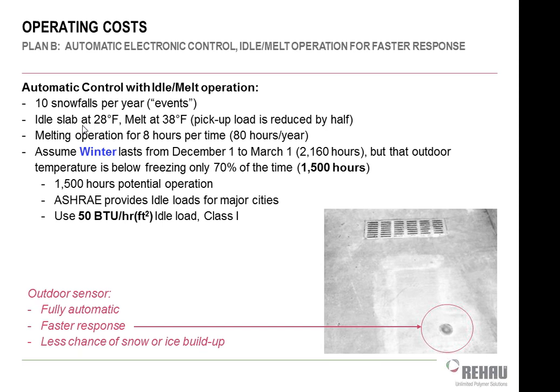We need to get up to 38 degrees of slab temperature to actually melt this snow, which is going to mean we're going to have to send 80, 90, 100 degree water out there. Once again, it's 80 hours of operation in this scenario. But because we have that idle slab, it's a little bit more energy use. So showing you there the 1,500 hours of potential operation.